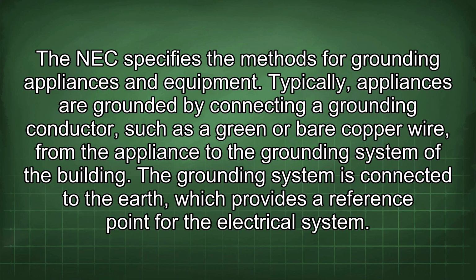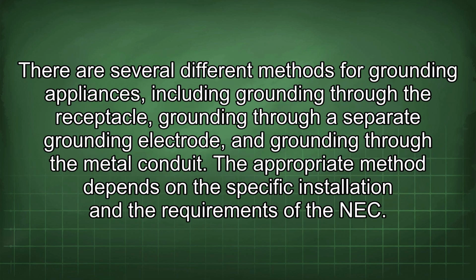The NEC specifies the methods for grounding appliances and equipment. Typically, appliances are grounded by connecting a grounding conductor, such as a green or bare copper wire, from the appliance to the grounding system of the building. The grounding system is connected to the earth, which provides a reference point for the electrical system. There are several different methods for grounding appliances, including grounding through the receptacle, grounding through a separate grounding electrode, and grounding through the metal conduit. The appropriate method depends on the specific installation and the requirements of the NEC.